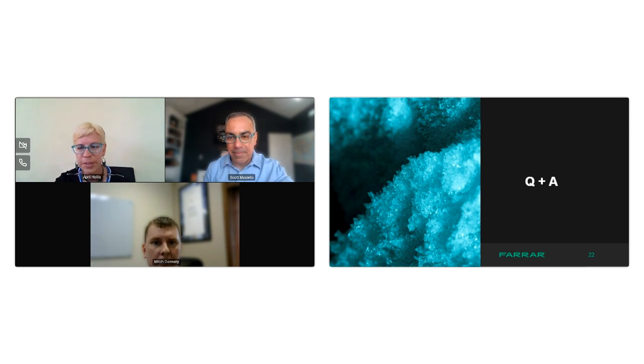Okay, and where is the position of the control probe in a negative 80 degrees Celsius ULT? So in our ULC, which is our larger chamber, it's in the middle of the chamber in between the two doors. And there's one probe for each machine section. And then the machine that is running at that time is the control probe that we're using. So it's displayed out on our HMIs. For the ULT, it's, I believe, in the bottom lower middle in the back of the unit.